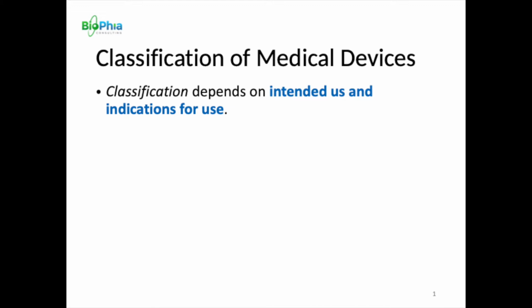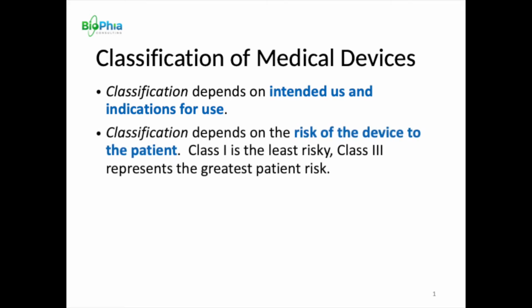And so the classification depends upon the intended use and the indications for use, first of all. Second of all, it depends upon the risk level of the device. And sometimes even if it's a class 2 device, as I said, the FDA may say, this is a little bit riskier. You're going to need to go through a de novo application for this, a little bit more data that's needed by the FDA in order to judge its safety and efficacy.